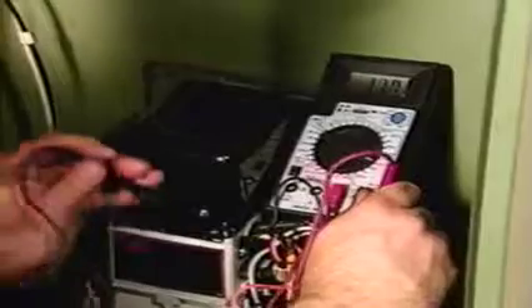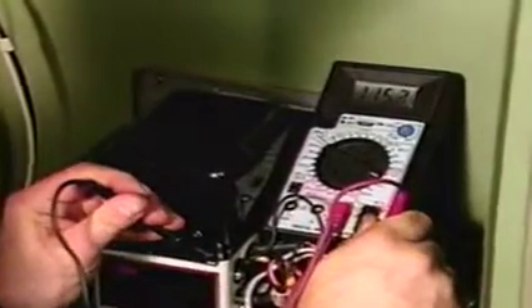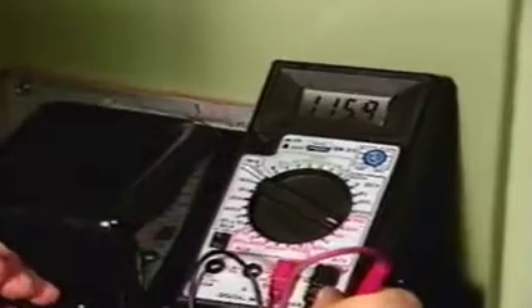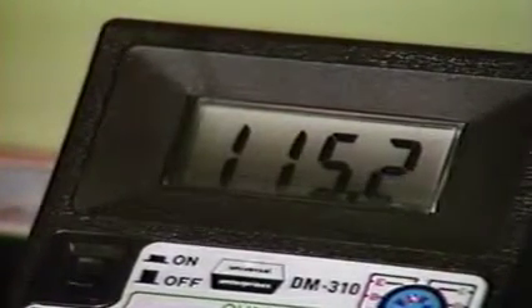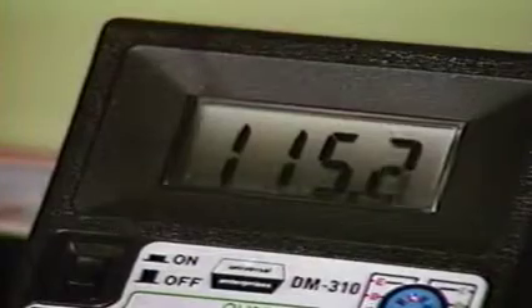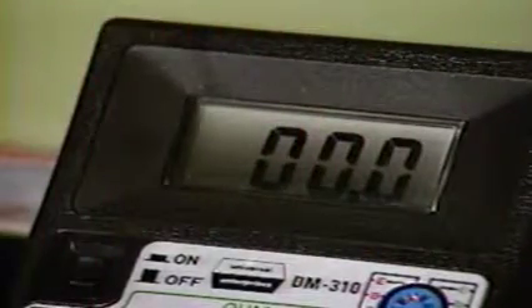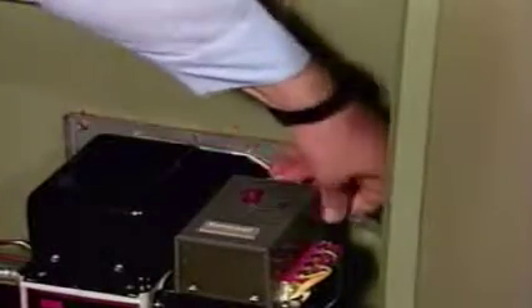After removing the oil, measure the line voltage at the primary control input connection, observing standard electrical safety procedures. The voltage should be 115 volts. A voltage lower than 105 volts may cause an operating problem. If there is no reading at all, check for open switches or circuit breakers in the supply line. If the line voltage is normal, remove the primary control cover. If the safety reset switch is in the up position, it is on safety and the line is locked out. This indicates an electrical problem or a problem with another system.